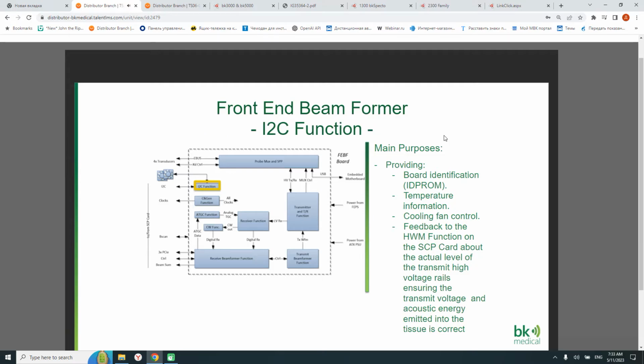The I2C function is providing board identification, the ID prom. It's providing cooling fan control and feedback to the hardware monitor function on the SCP card about the actual level of the transmit high voltage rails. This is to make sure that the transmit voltage is actually what it is programmed to be and that the acoustic energy emitted into the tissue is under control.